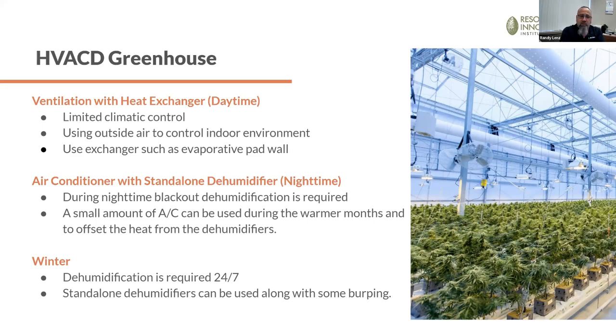Sometimes we can do a little bit of exhausting, but a lot of people don't want to open the curtains over the exhaust either and bring in any light to wake the plants back up. So we've found it successful in most greenhouses to have a bit of air conditioning during the nighttime hours to offset that heat, because it's blacked out, so you're not letting heat in from the outside, it's just heat left over from the daytime process and the dehumidifiers. If you put in a little air conditioning, it really helps with the dehumidification, and you can control that humidity and temperature very well at night.